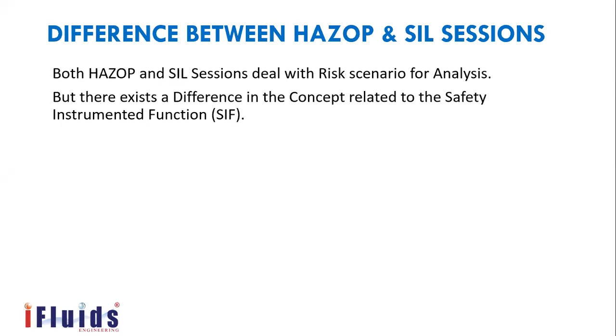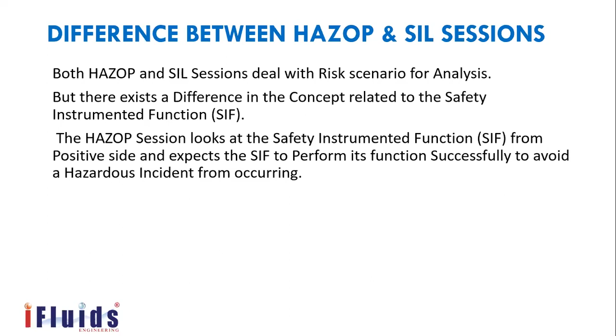But what is the difference here? The major difference is that the HAZOP session considers the SIF, that is, the safety instrumented function. A safety instrumented function means a low level trip, low temperature trip, high temperature trip, or low pressure or high pressure trip, without even human intervention. The system functions automatically without human intervention. This is a major thing. The HAZOP considers the safety instrumented function on the positive side, assuming it works, and gives it the credit. But what LOPA does is look at how credible this safety instrumented function is, whether it can fail, and what the consequence should be if it fails.